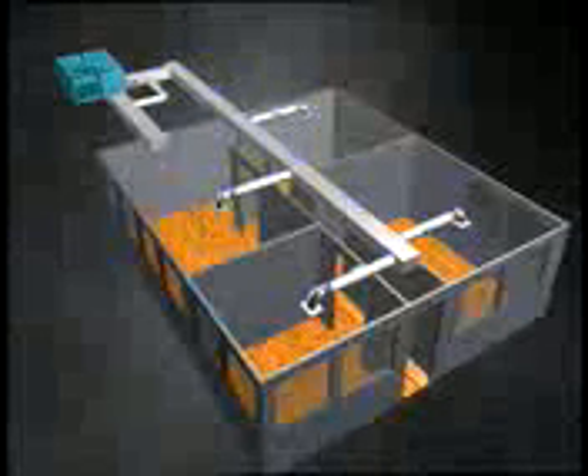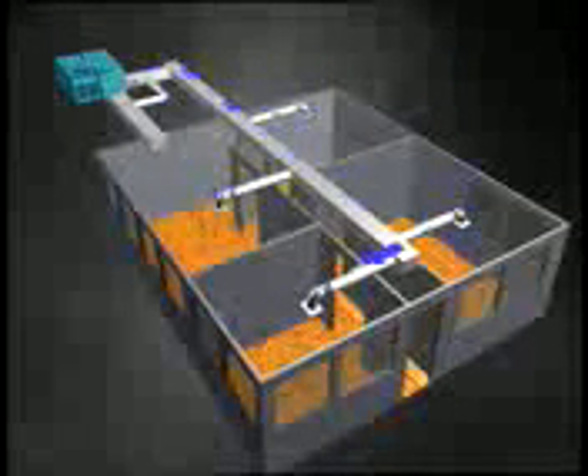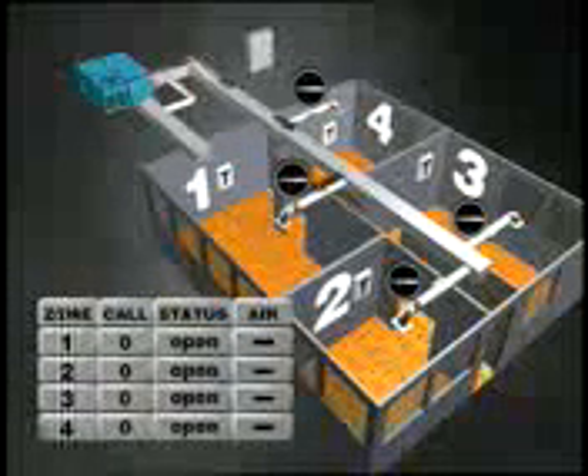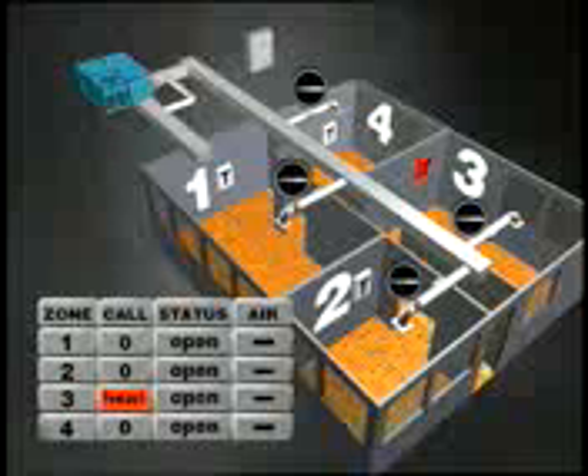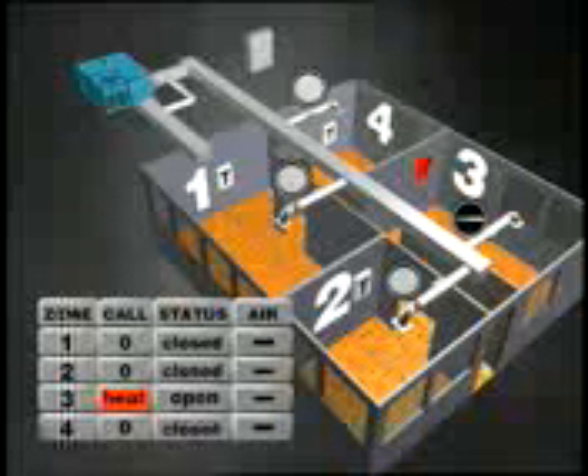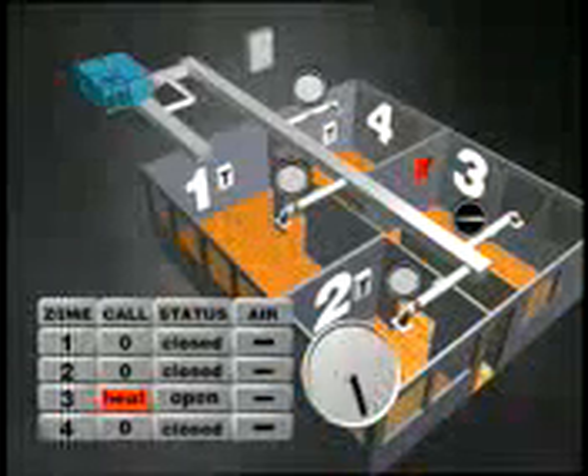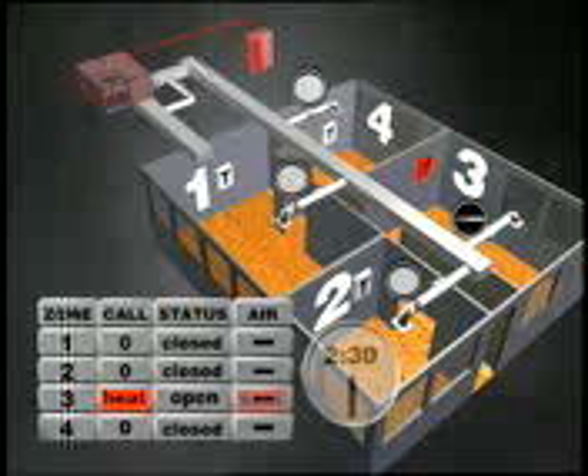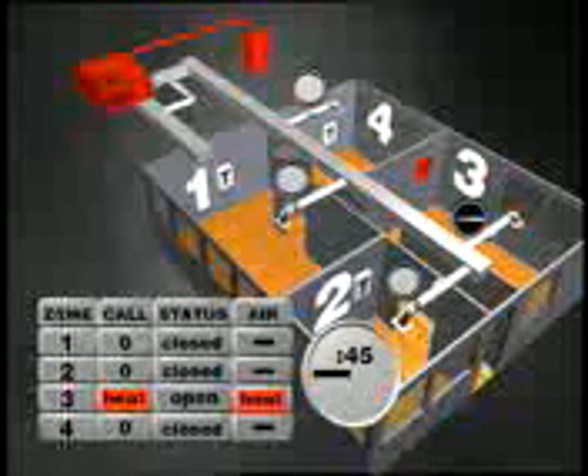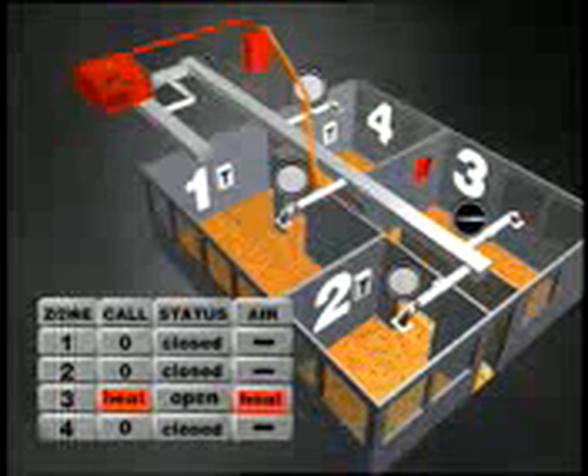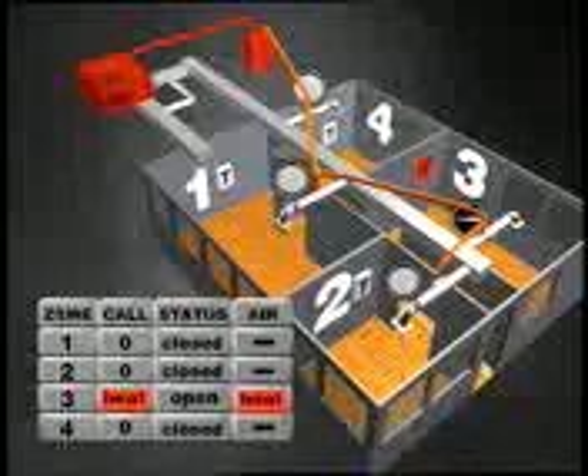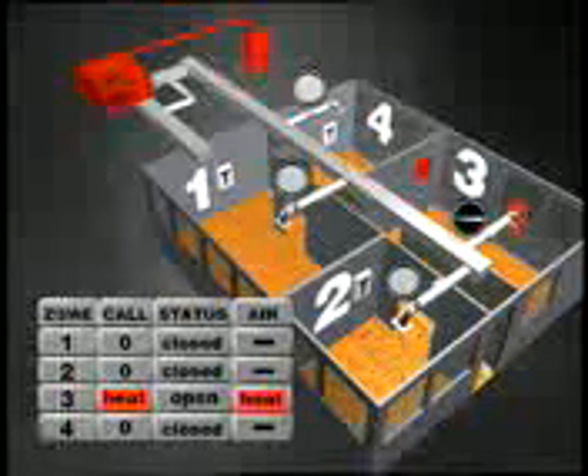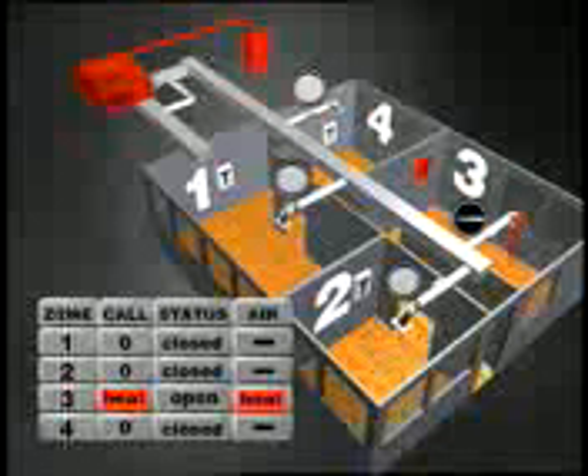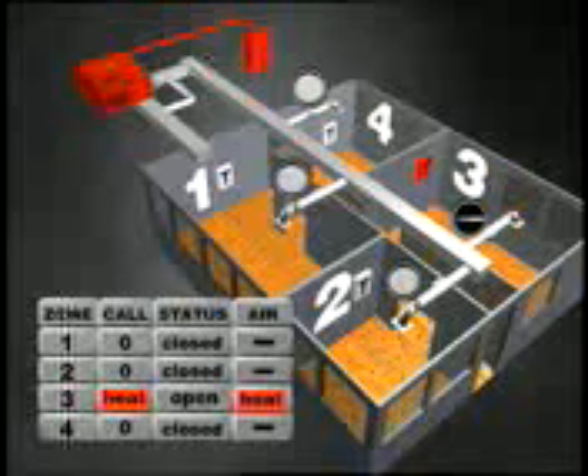Here's how it works. As our example, we'll use a vote-based auto changeover controller that operates first call, first serve, majority wins on changeover. With all zones open and air circulating, Zone 3 calls for heat and Zones 1, 2, and 4 drive closed. After a 2.5-minute delay to prevent short cycling, the controller turns on the heat. Every 45 seconds, the controller polls the system to determine if other zones require heating or cooling. This polling continues until the temperature requirements for Zone 3 are satisfied, or until more zones demand a change.